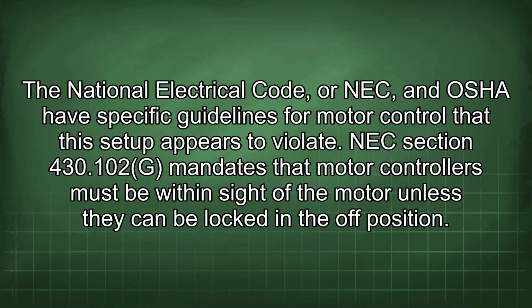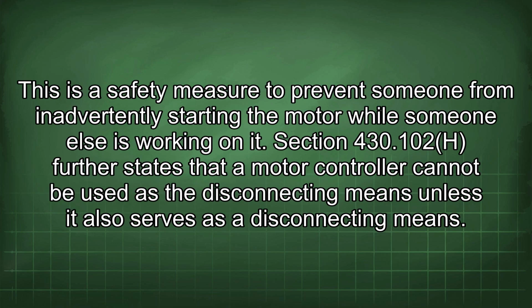The National Electrical Code, or NEC, and OSHA have specific guidelines for motor control that this setup appears to violate. NEC Section 430.102G mandates that motor controllers must be within sight of the motor unless they can be locked in the off position. This is a safety measure to prevent someone from inadvertently starting the motor while someone else is working on it.